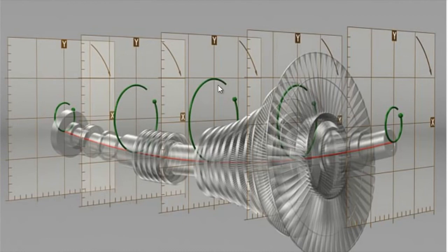Now we may not be able to put proximity probes in all these locations, I'm just showing this for illustrative purposes, but this is the orbit, and that orbit tells us it may be small and circular, that's good. It may be bigger and elliptical, and then we have to start to ask, well, is that okay? Could it mean there's some preload or misalignment? If it gets big, then it could be the oil whirl we just looked at, or oil whip.